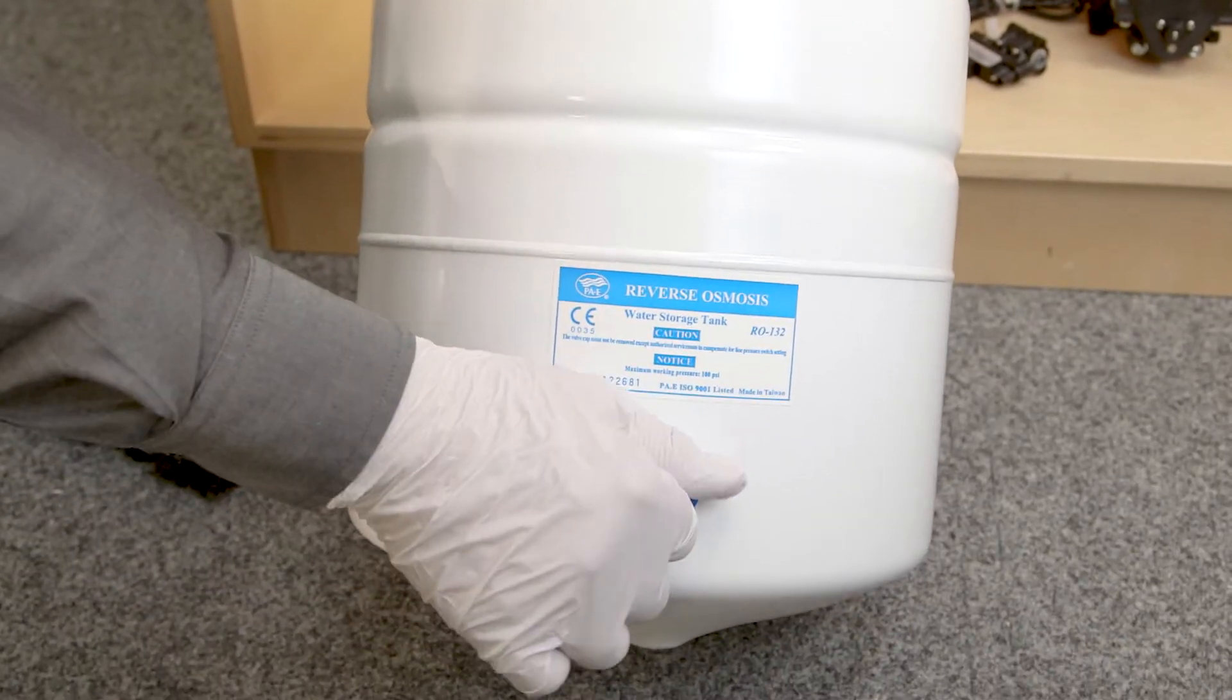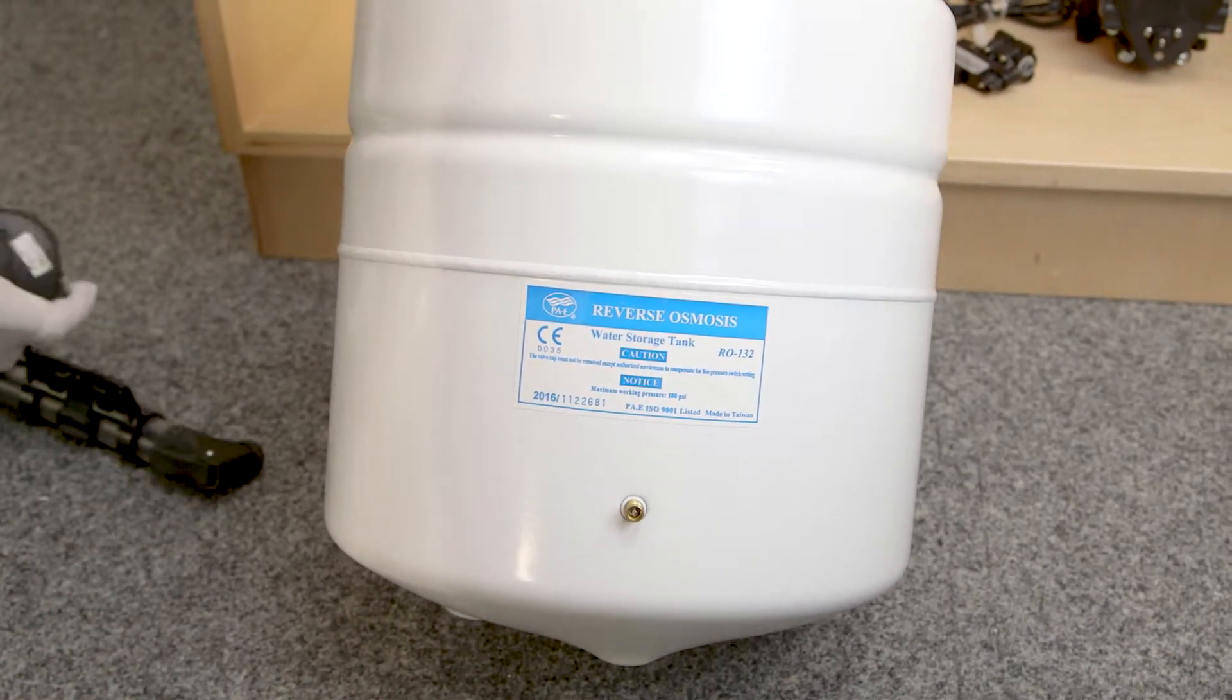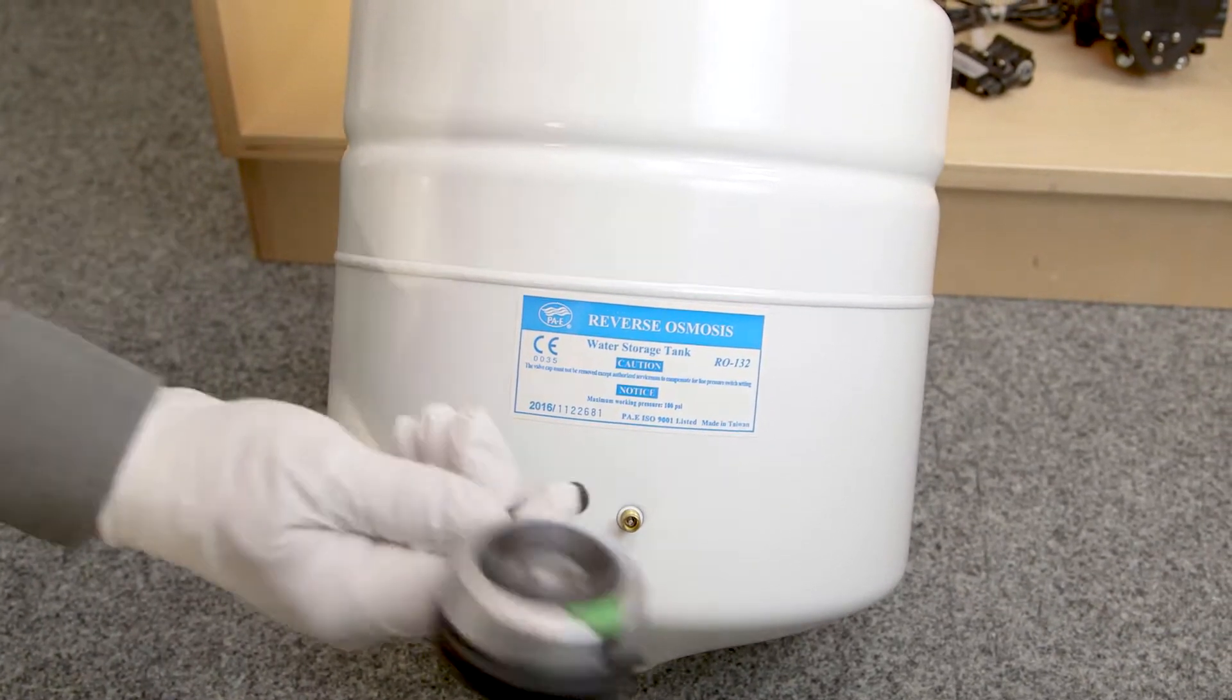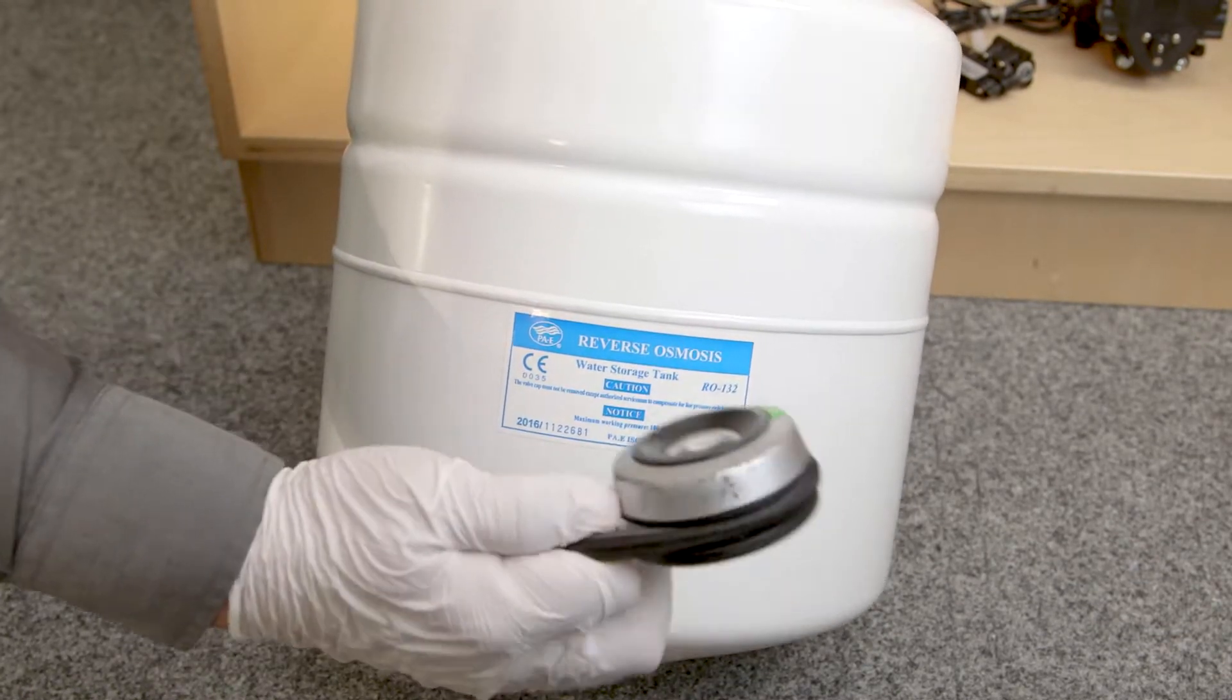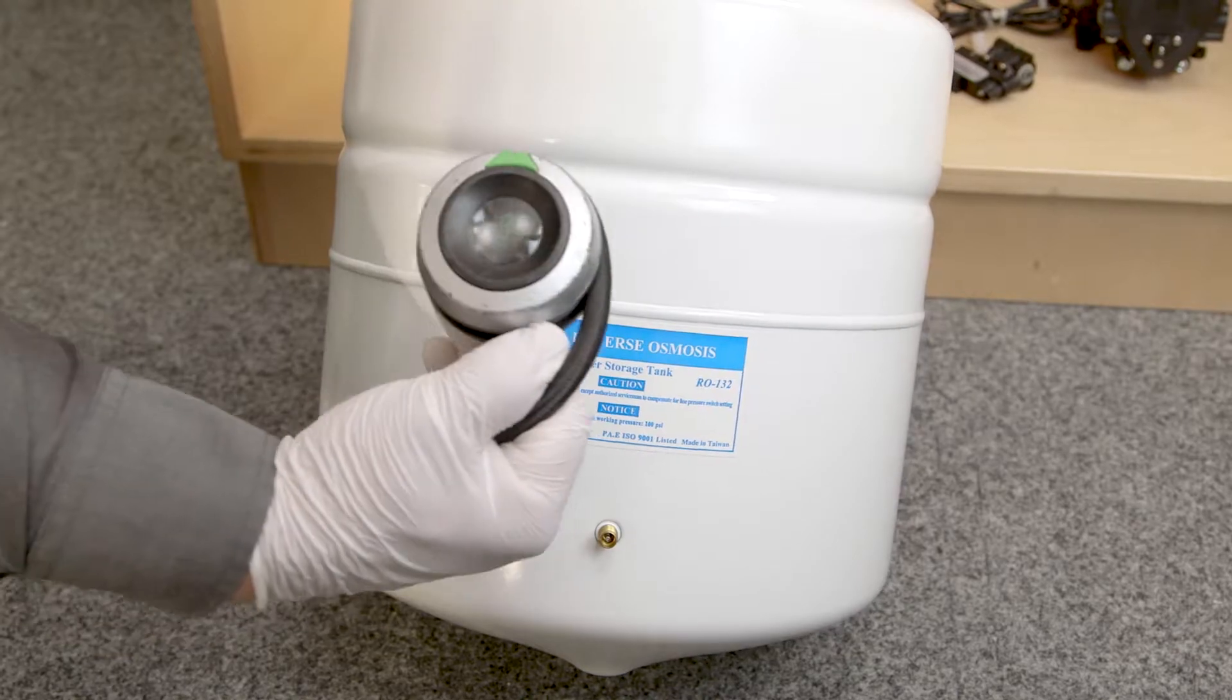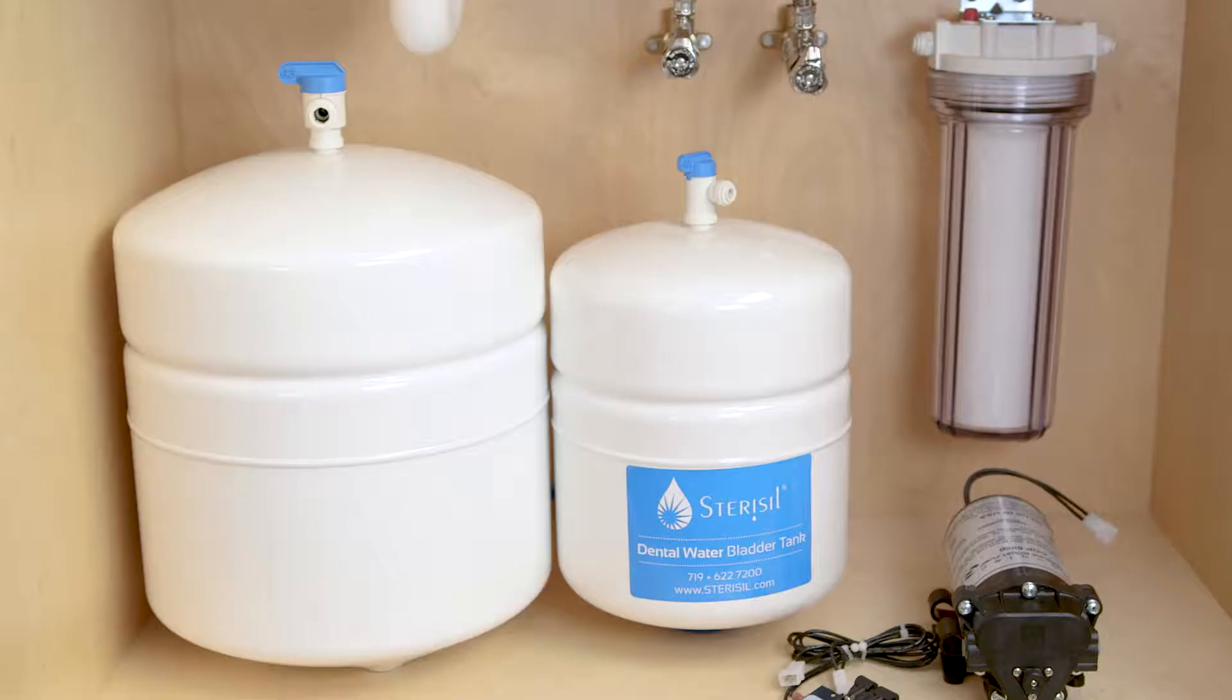On the tanks, you'll find a plastic blue cap. Rotate it counterclockwise to remove it, exposing the Schrader valve. Verify the pressure is between 8 and 10 psi. If they're not within that range, you'll need to add or remove air with your low volume air pump. Your tanks are now ready for plumbing.